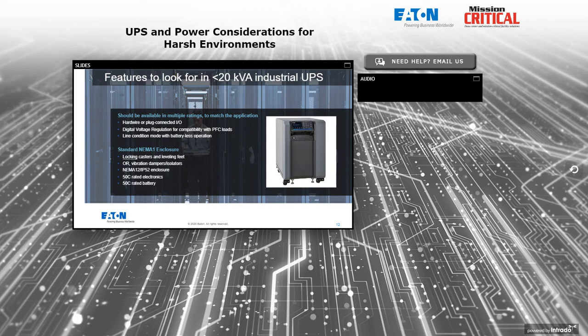That's a key feature for this type of system as well. Standard enclosures, at least NEMA 1, in some cases much more resistant, chemical resistant enclosure, but you're looking for things like not just casters and leveling feet, but locking casters. These UPSs are heavy like all UPSs, and you do not want them rolling away. So locking casters are a requirement. You see casters that don't lock, that's a bad sign.